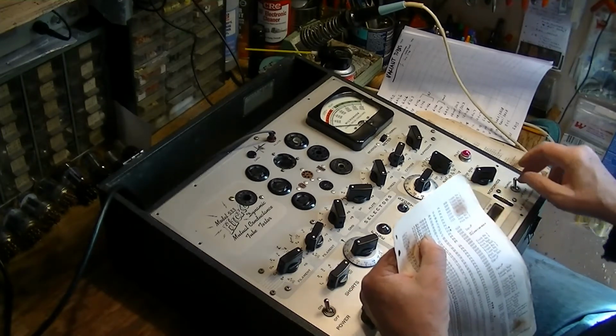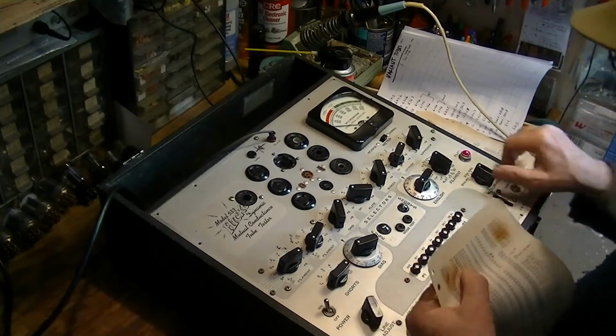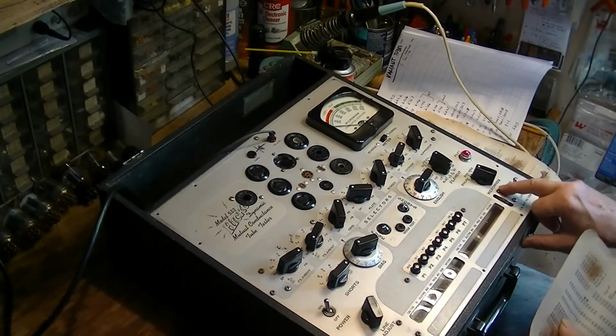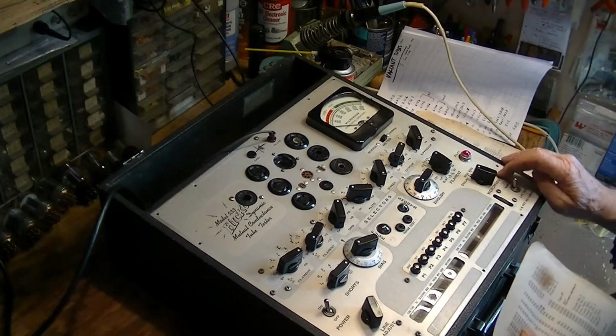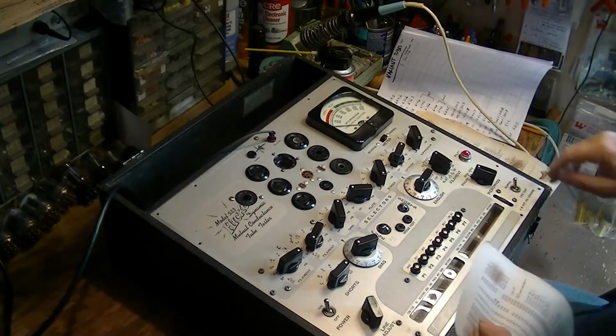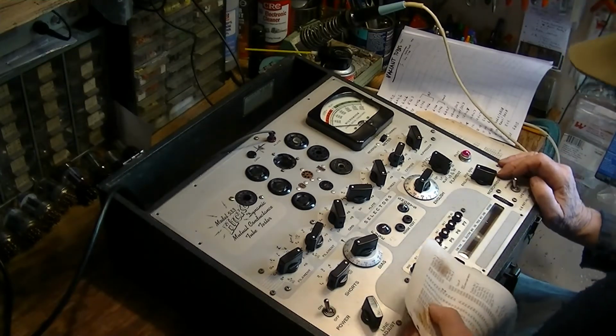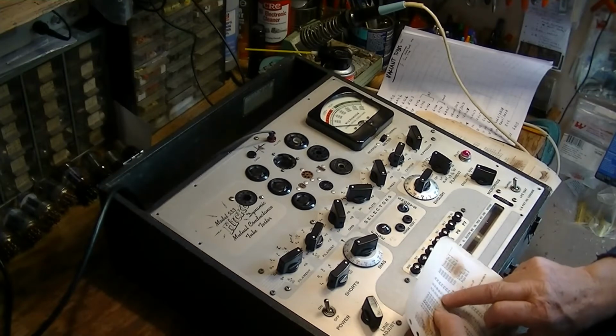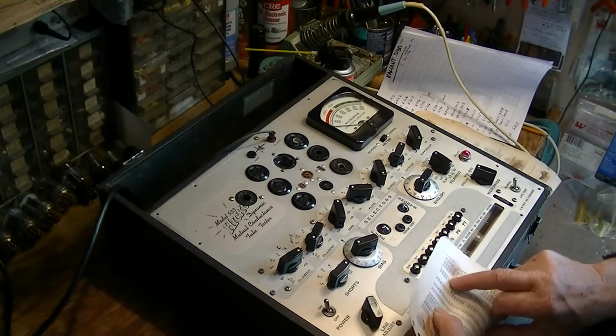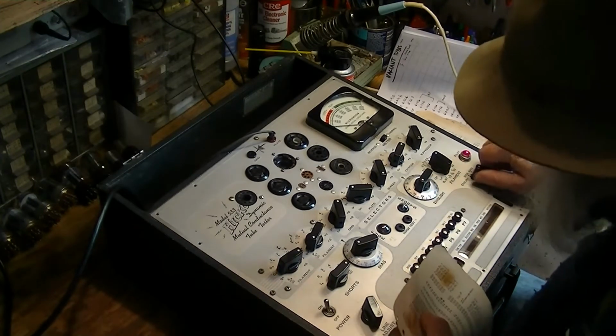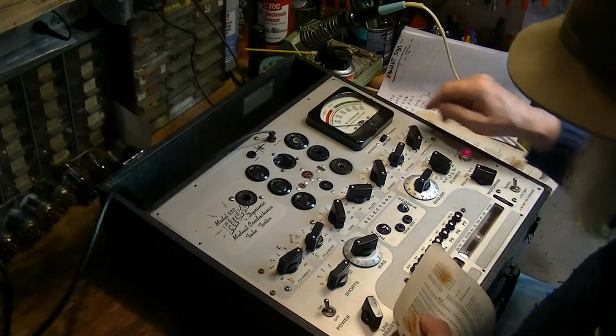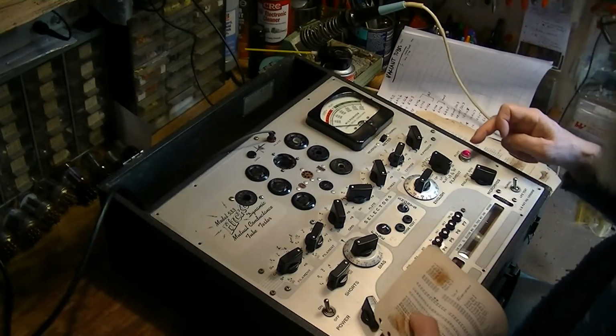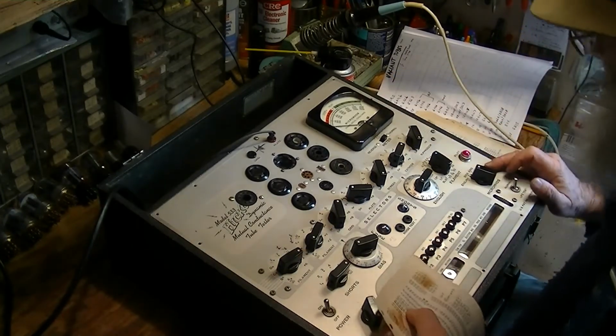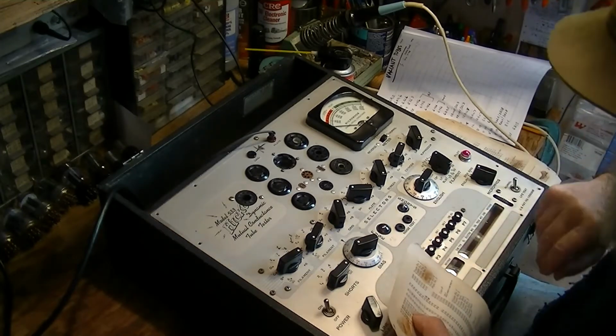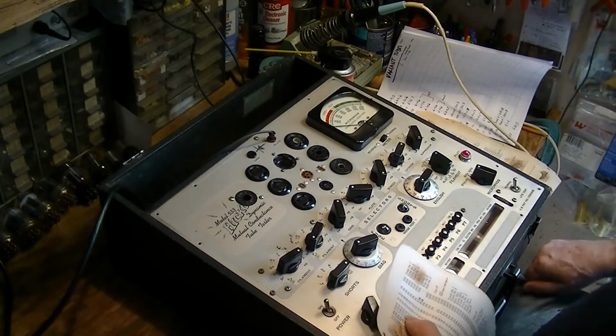The other thing you have to do is set the range for the transconductance. It says Micro Mhos, and that's the scale that you're reading transconductance in. So this one is going to read 2200. So we're going to go for 3000 full scale. You get a choice of 3000, 6000, or 15,000. I very seldom ever seen a tube that goes that high.